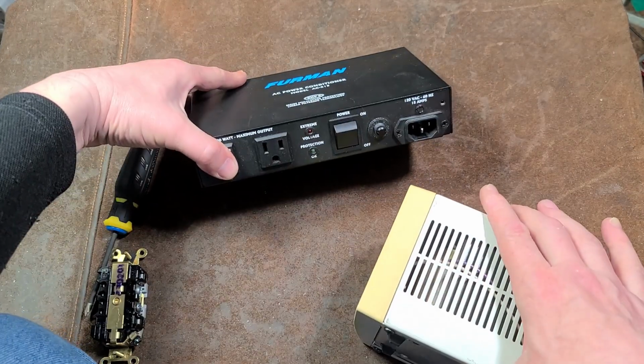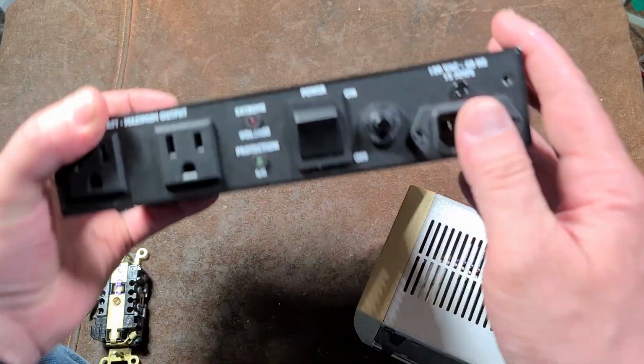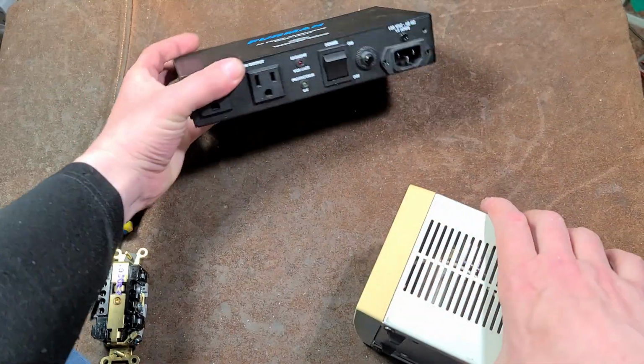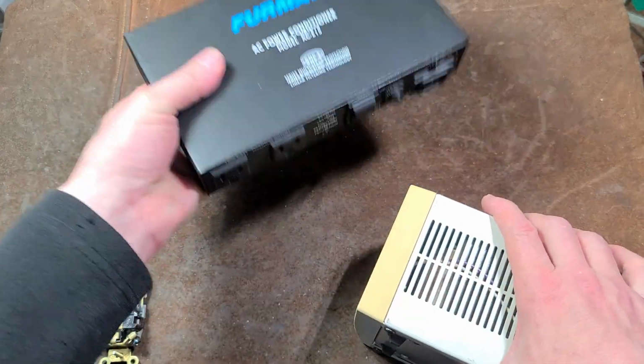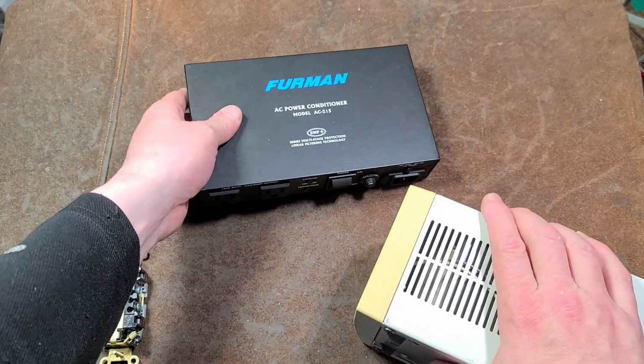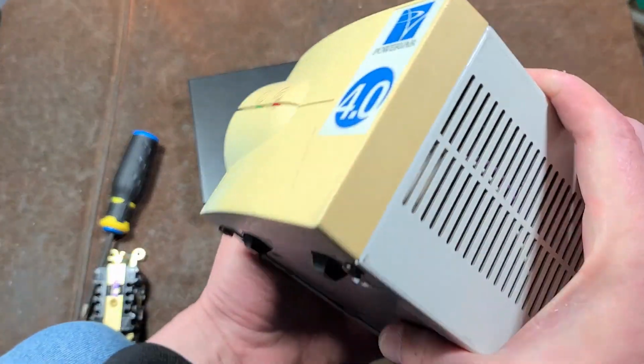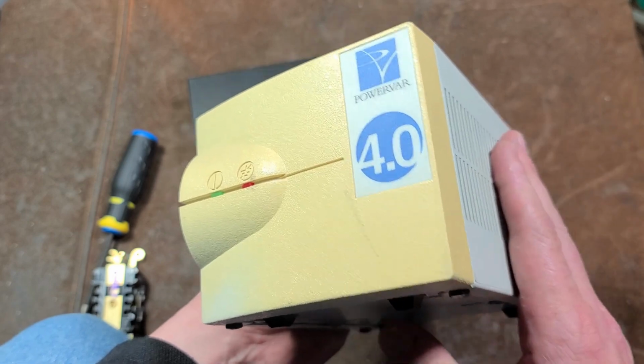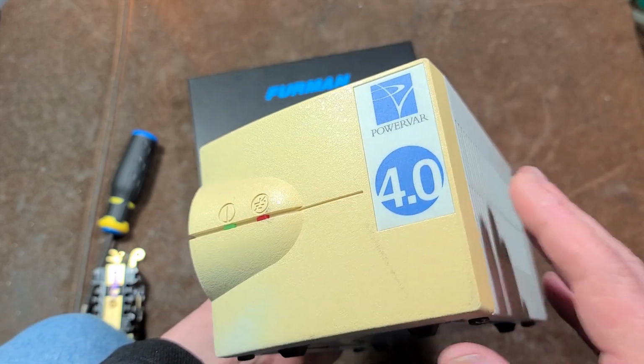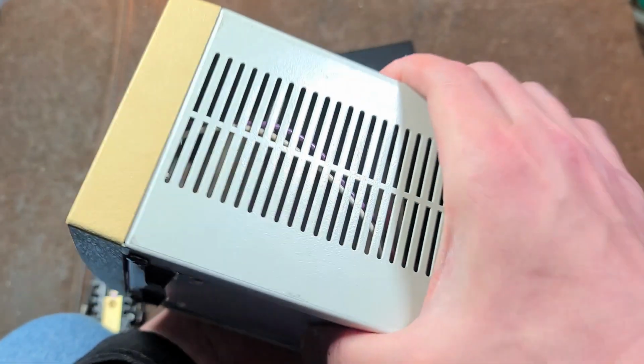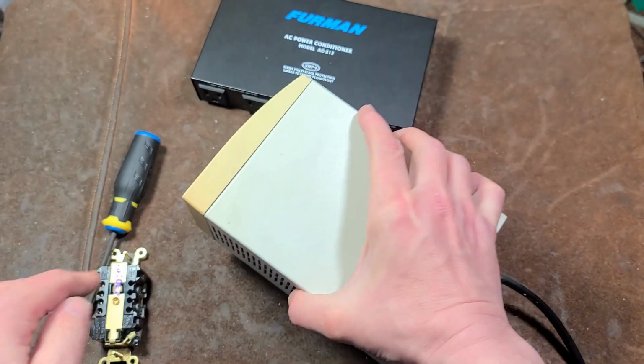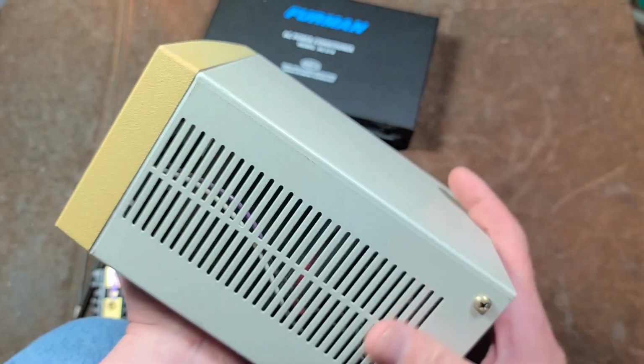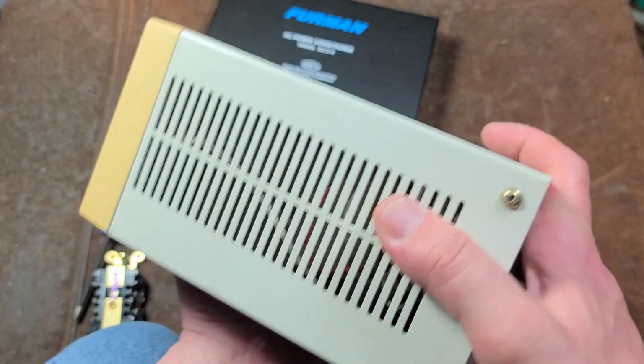This is rated for 1800 watts, 15 amps. You can see its size and weight, and it's pretty heavy duty, pretty heavy for a line conditioner, but it's not really a power conditioner, a transformer-based isolation power conditioner like this Powervar. You can see the size and weight of this. It's a transformer, and it's only rated for 4 amps. So that gives you an idea if you're actually dealing with a real isolation transformer.